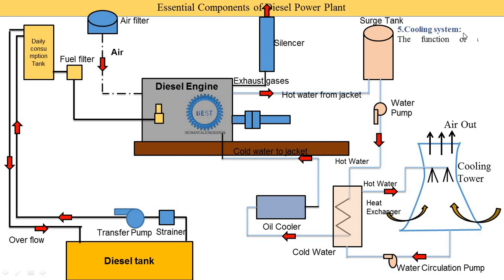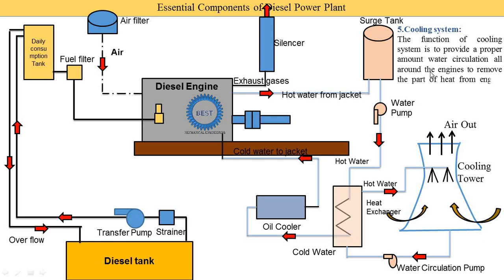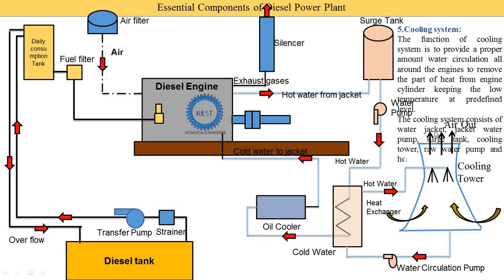The function of the cooling system is to provide proper water circulation around the engine to remove heat from the engine cylinders and keep temperatures at predefined levels. The cooling system consists of the water jacket surrounding the cylinders, the jacket water pump, the surge tank, the cooling tower, the raw water pump, and the heat exchanger.